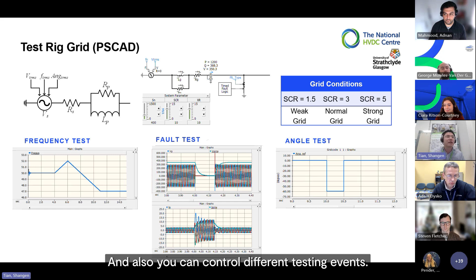Where did the test plan come from? This came from the GB Grid Forming Test Guidebook, published by NESO in April 2023. It's mainly two parts - grid code compliance testing, and also small signal scan.